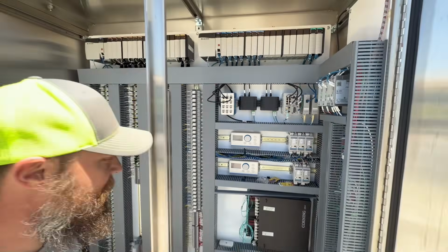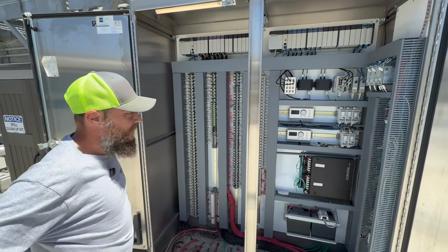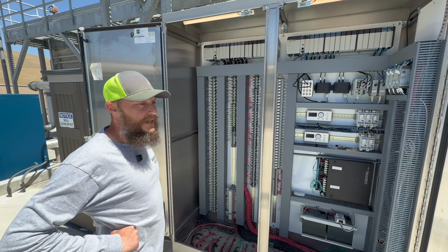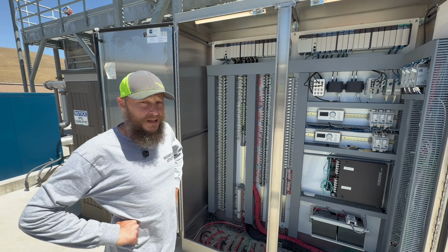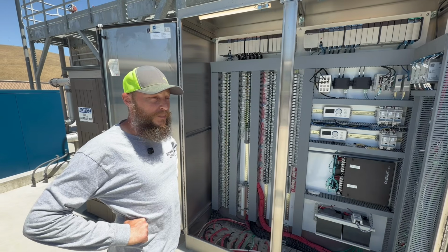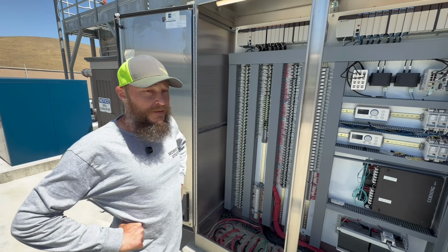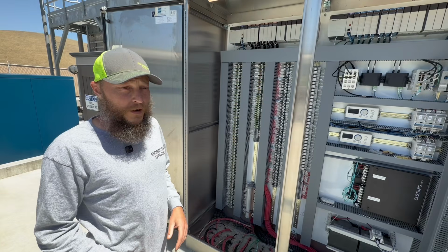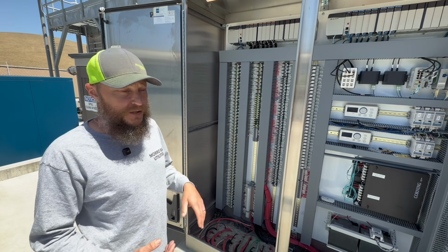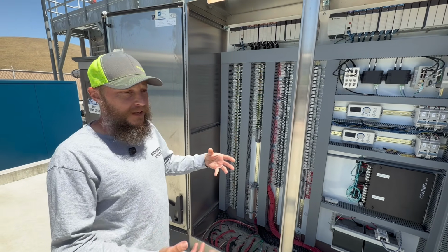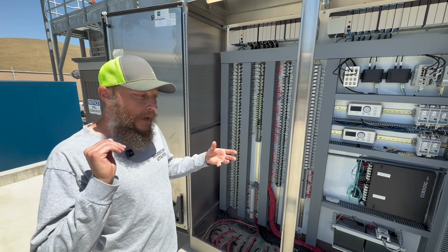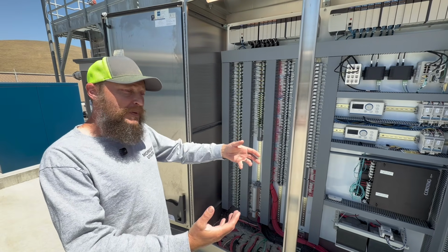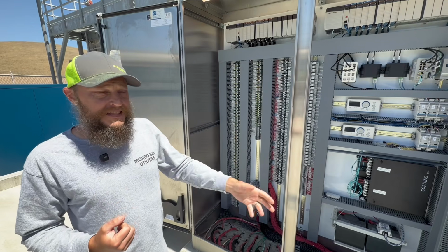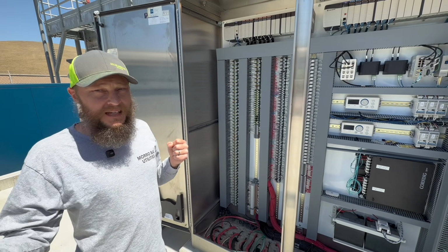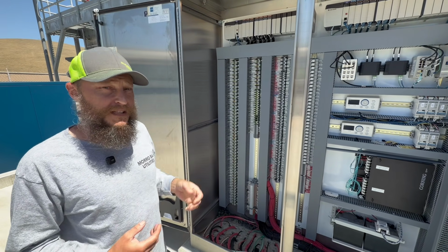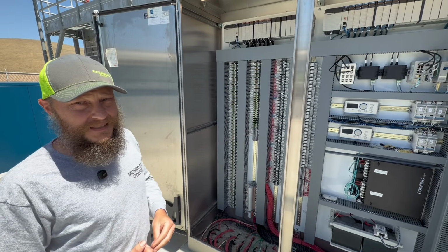Very cool. Okay, so inputs, outputs. So output goes to the HMI, does it not? No, the output goes to the field device. Okay, so what's the input? So the input would be a motor state or a transducer reading. If you have a level transducer, that level transducer is going to be sending a signal that the PLC is taking as an input. It's taking that number in, and then SCADA, or the code that controls the facility, can use that number in the process. Gotcha. Interesting.